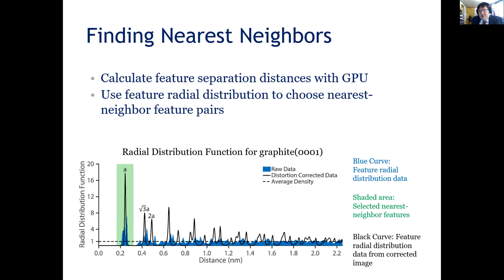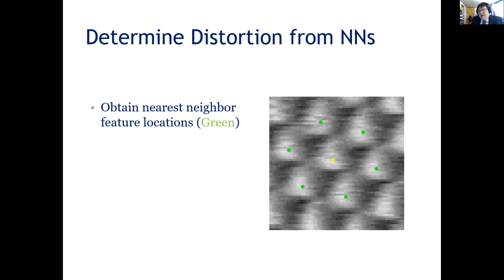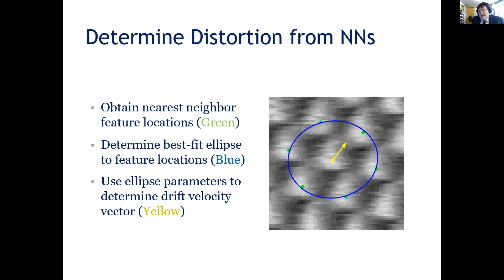Once we have feature locations, here's an example of how we would calculate the distortion. We want to calculate the distortion at this yellow point. So we get the nearest neighbor features in green. We find the best fit ellipse to them, which should be a circle in an undistorted image, but it's an ellipse because the image is distorted. We calculate the distortion that would cause a circle to become this ellipse, and we label the distortion at that point by that drift velocity vector.